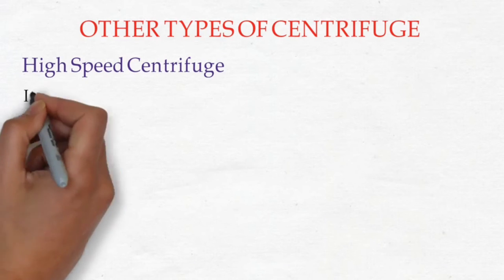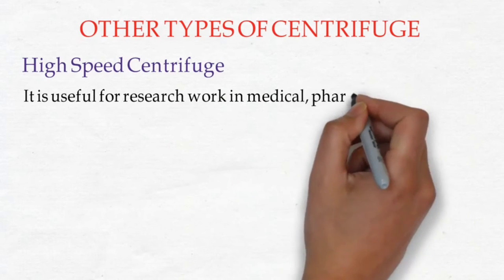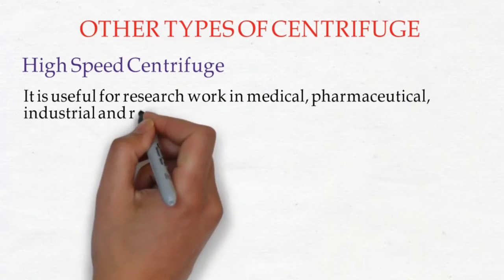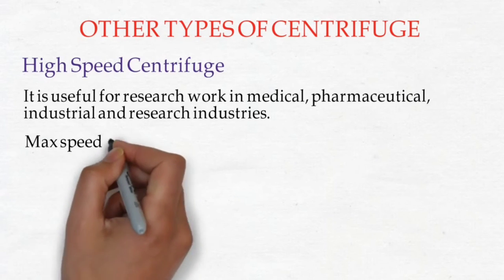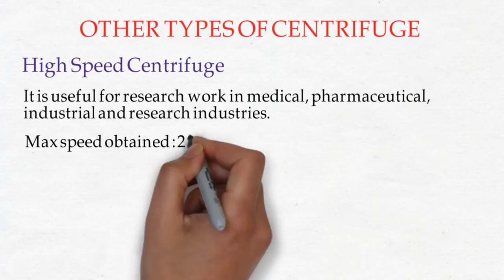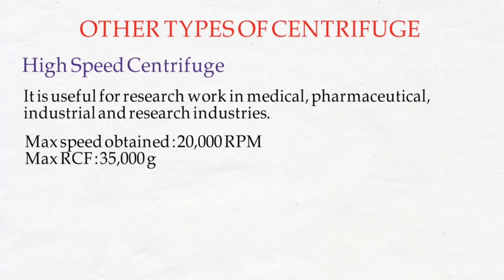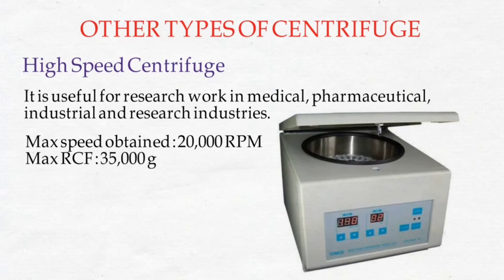Now we will see other types of centrifuge. The first is the high speed centrifuge, useful for research work in medical, pharmaceutical, industrial, and research settings. The maximum speed achievable is 20,000 RPM and a maximum RCF of 35,000 times gravity. Here is a working model example of it.